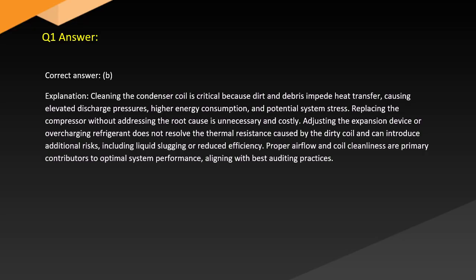Cleaning the condenser coil is critical because dirt and debris impede heat transfer, causing elevated discharge pressures, higher energy consumption, and potential system stress. Replacing the compressor without addressing the root cause is unnecessary and costly. Adjusting the expansion device or overcharging refrigerant does not resolve the thermal resistance caused by the dirty coil and can introduce additional risks, including liquid slugging or reduced efficiency. Proper airflow and coil cleanliness are primary contributors to optimal system performance, aligning with best auditing practices.